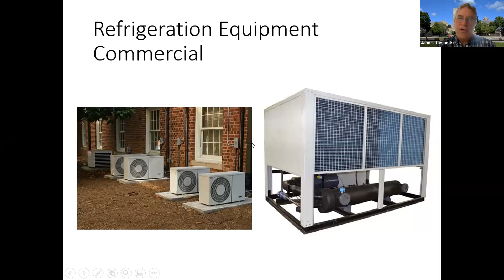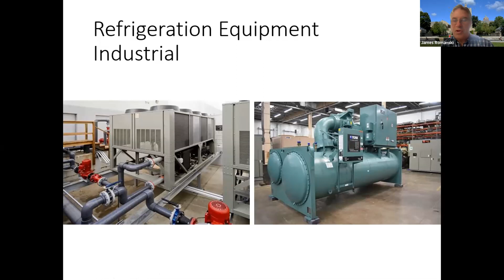But generally speaking, for a power plant, you'd be looking at some kind of large chiller. These chillers don't use fans and air to cool their hot side. Instead they use cooling towers and water to evaporate and cool, using the latent heat of vaporization, which is a much more efficient way to cool down. But having a cooling tower and a large system like this is quite complicated, so it's more efficient, but really only available to those doing cooling on a large scale.